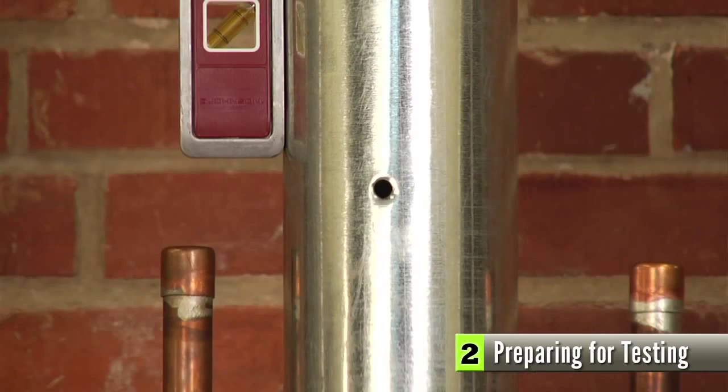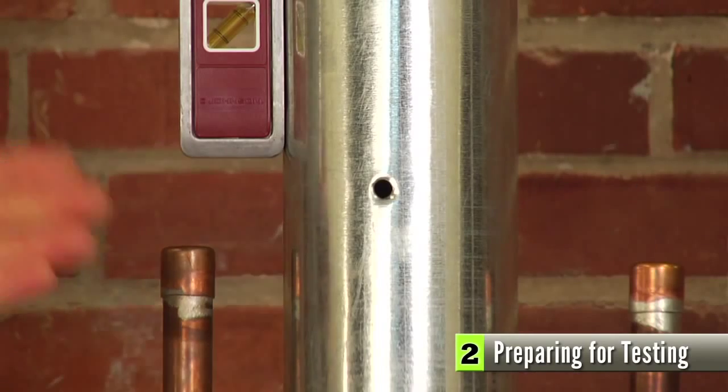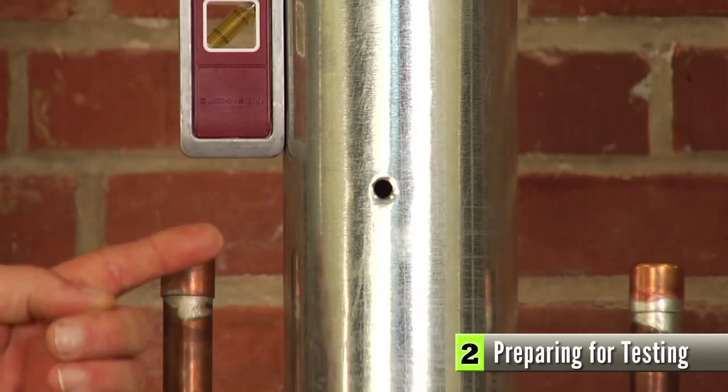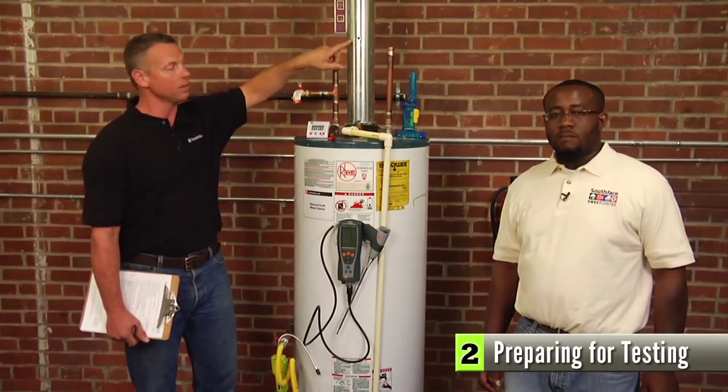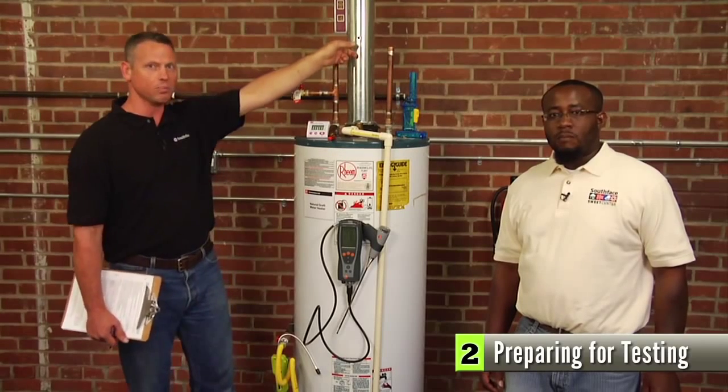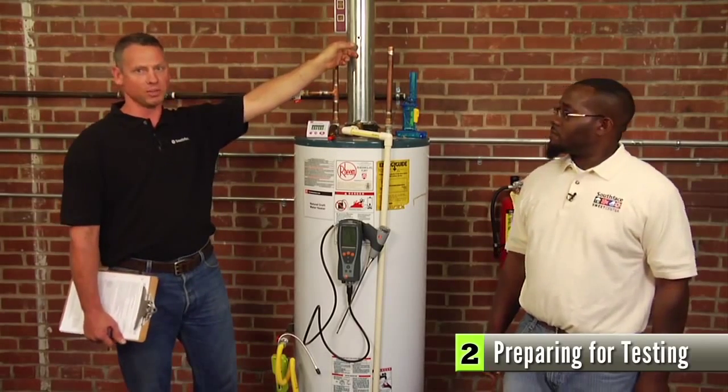Got it. Okay. Next, we need to drill a hole in the flue pipe 1 to 2 feet above the draft diverter or after the first elbow. And don't get too hung up on those dimensions. They're not critical. Just anywhere above the appliance. Now this hole's already been drilled, and this is just a single wall pipe. If this pipe had a double wall pipe, a B vent, then we would make sure that we drilled all the way through both walls so that we could fit our static pressure probe in.